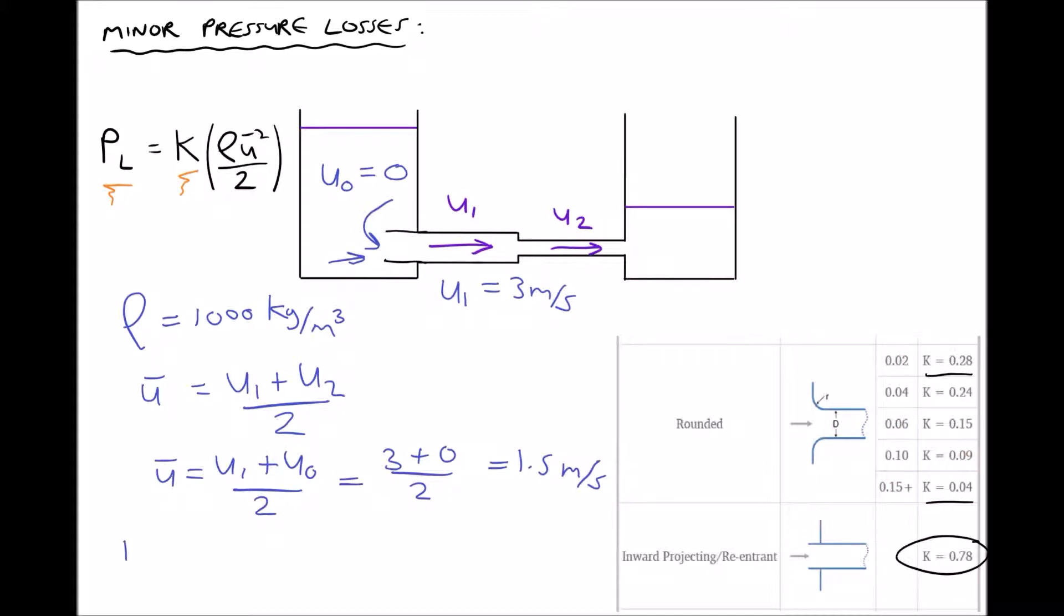So with that being said, we can calculate our pressure loss. Our pressure loss is K, and from our table we know that K for an inward projecting pipe is 0.78. In the brackets we have our density 1000 times ū bar squared, 1.5 squared, divided by 2, giving us a pressure loss equal to 878 pascals. So we're dealing with relatively small pressure losses here.